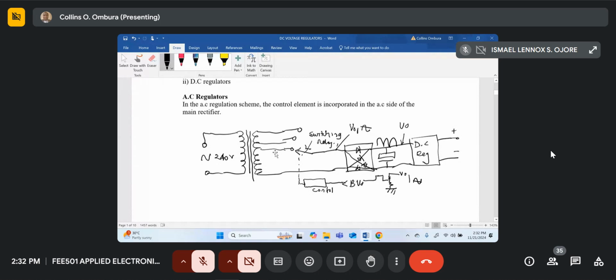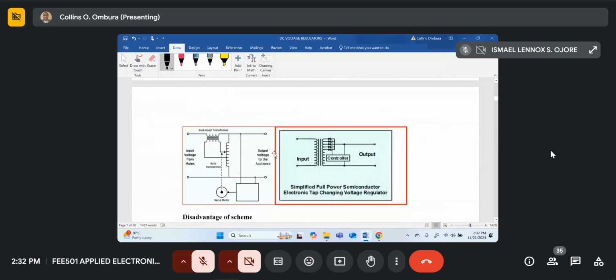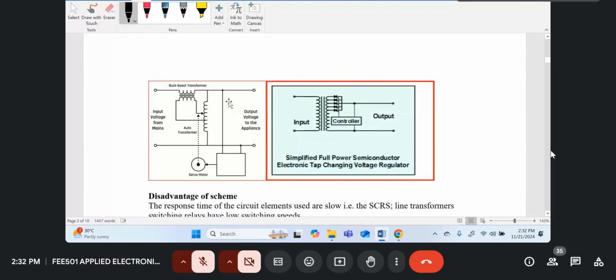This is one scheme, but there are actually four schemes. I've imported some diagrams here. The first uses a servo motor—this is the control circuit, which monitors the output so you get a constant AC output. You've got an auto transformer, and the servo motor changes the tapping depending on the AC side voltage. If the voltage falls, the tapping moves upward to add to the transformer voltage. If the voltage drops further, the servo motor is driven to the bottom part.